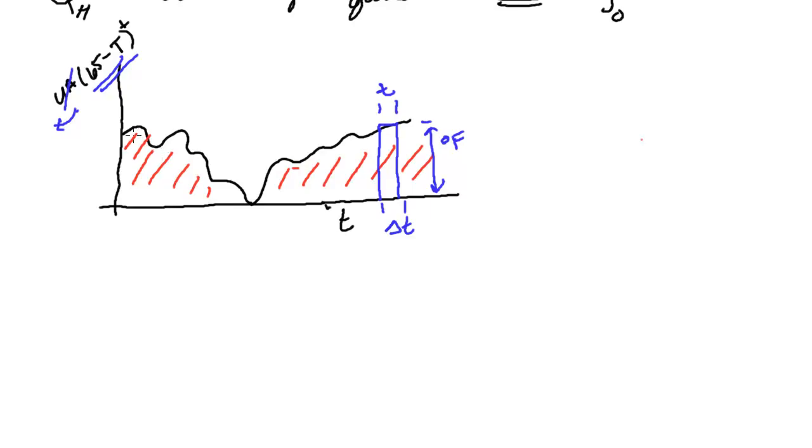Now to make it a degree day, all it's saying is that, okay, this is, let's say this is Jan 1st at midnight. And I'm going to make this bigger than what it really would be. But let's say this is Jan 2nd midnight. So this is one day difference. Well, we can approximate that area by taking the average temperature of that day. Average temperature, degree, we'll say that's 30 degrees F. And multiply it by the difference of one day. Degree day. 30 times 1, 30 degree days. It really should be degree F days, would be a better nomenclature. And so then we take this temperature data throughout the whole year. We take the average daily temperature. And we multiply it by one day and we sum them up. And that gives you a total degree days.